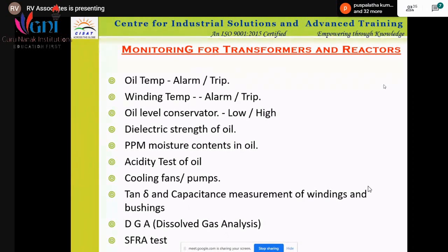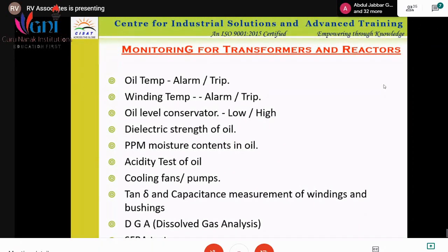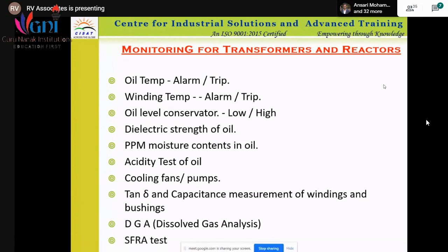Then there is the oil level in the conservator. Normally it is half filled. Whatever we have studied, the conservator oil level is almost 50%. The level indicator can show low and high. Then the dielectric strength of the oil, and the ppm moisture content in the oil. These are all the monitoring parameters that we use, and this monitoring of oil gives you a direct indication of what type of fault is there in the transformer.